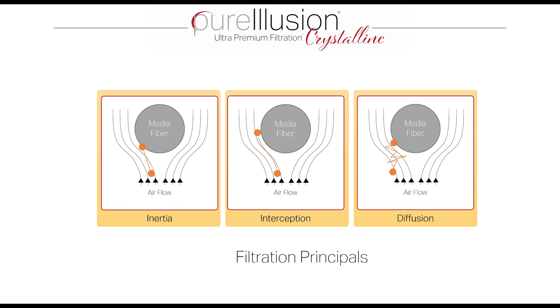Interception of a particle occurs on smaller particles — those that are carried by the airflow floating around the media fibers. When a particle is small enough to be carried by the airflow but large enough to be intercepted between the edge of the airflow and the media fiber itself, the particle becomes trapped by the interception filtration principle.